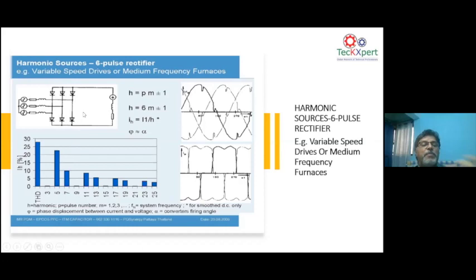Now, what happens in a 12 pulse drive? You don't have 5 and 7. You will see 11 and 13 as the starting harmonics, because NP plus minus 1 starts at 11 and 13. If you go for an 18 pulse drive, you will only see 17 and 19 starting. Nothing from below will be there. If you go for a 24 pulse drive, you will have only 23 and 25 as the starting harmonics. So sometimes consumers use a 6 pulse drive, and if it is producing harmonics, they may go for a 12 pulse, or an 18 pulse, or a 24 pulse.